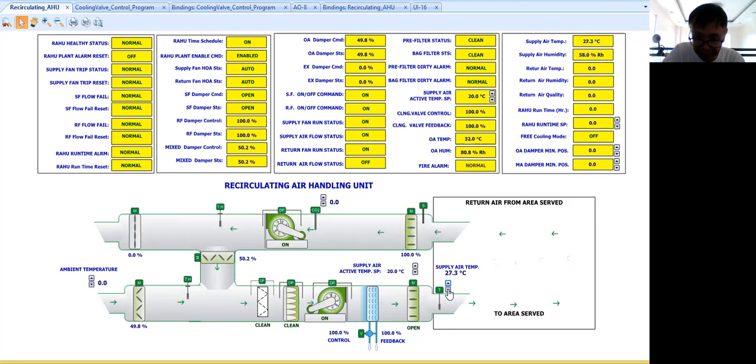Now let's say I'm trying to drop the temperature, okay? Now, still when it's 23, my control is still 100% for 10 volts, okay? Now, let's see if my valve will respond a little because there is still a 0.3 error there, okay? Now let's drop it to 19. Okay, we'll see if the valve will respond accordingly.